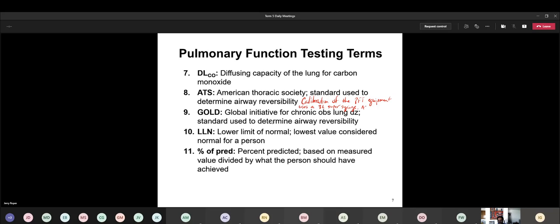And then ATS expects plus or minus 3% or 50 milliliters. Now, what that means is that the machine is going to guide you, almost like when you do SST on the ventilator, the machine will guide you through the steps that it wants you to do. With the calibration, your super syringe is going to be 3 liters always. That's what it's designed to hold. It's designed to hold 3 liters of air. And it's like a big plunger is what it is.